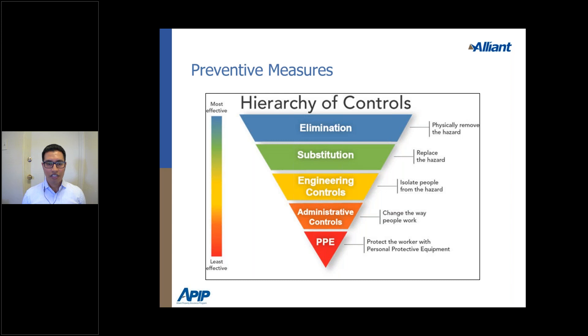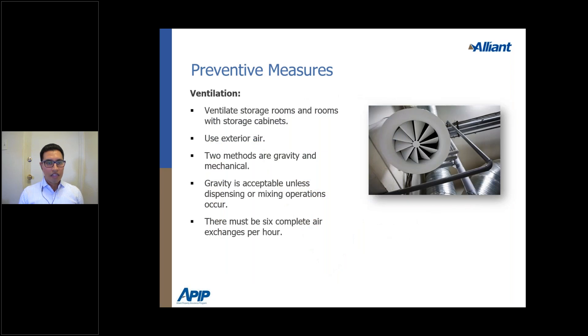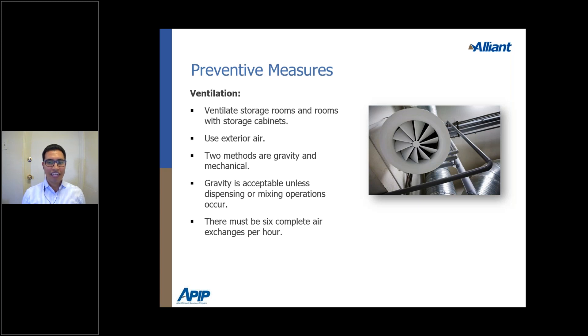Regarding ventilation as an engineering control: storage rooms and rooms with storage cabinets must be properly ventilated. For rooms simply storing flammables in cabinets, gravity ventilation is acceptable. However, for rooms used for transferring liquids, a mechanical ventilation system must be in place.